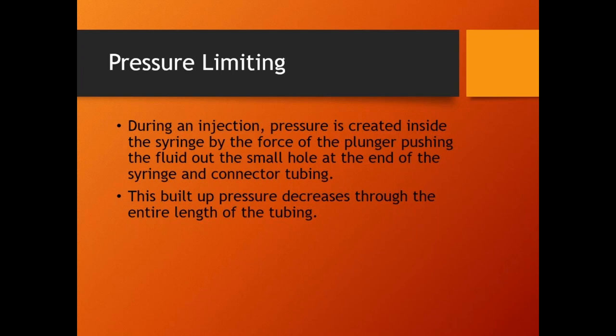So this is the three things: flow rate, volume, pressure, right? Now, the factor that affects your pressure limit the most, by far, is the flow rate. The faster the injection, the greater the pressure we're going to build up inside that syringe. All right. Let's say I'm connected here and I do a flow rate, and I'm forcing all this fluid out this little tiny hole at the top, with an even thinner tube coming out of it, through an even thinner IV needle inside the patient. All right.